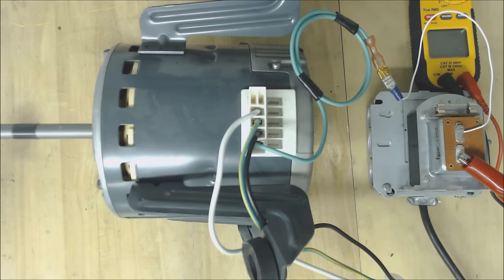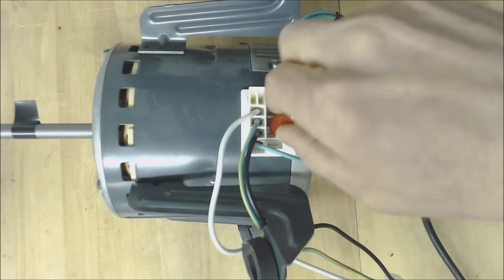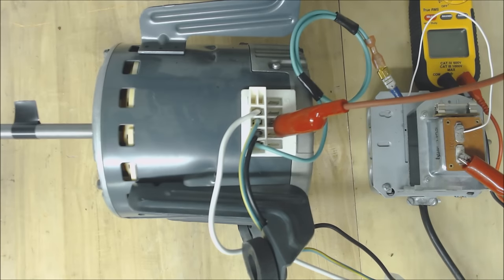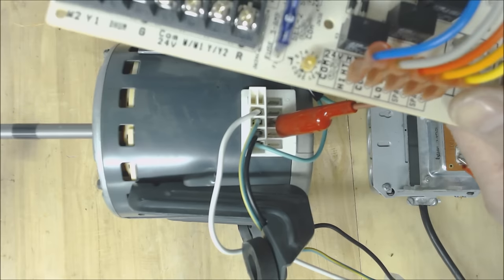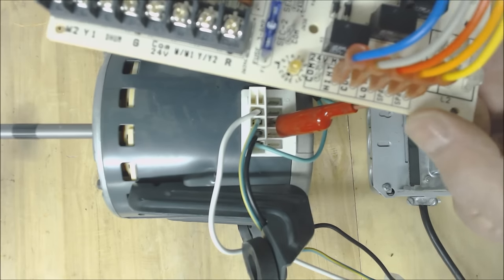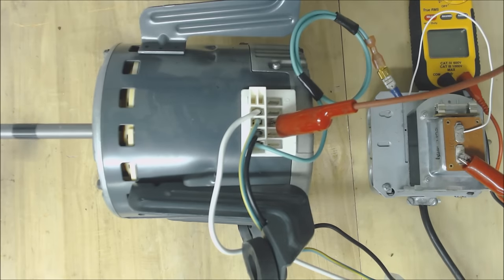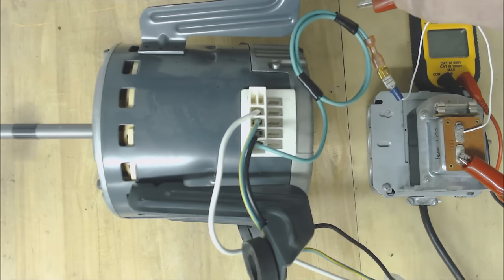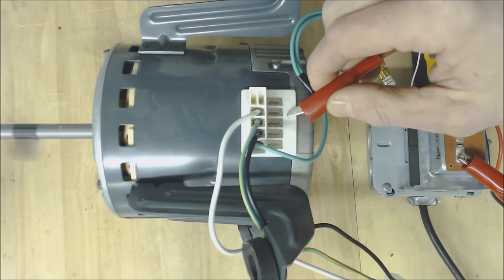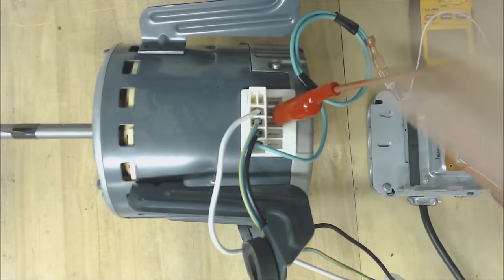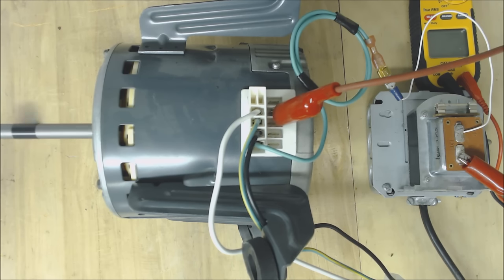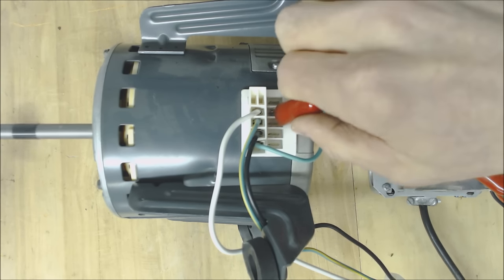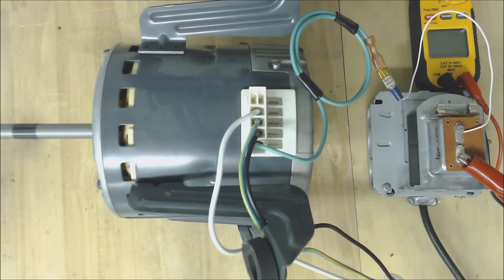It should be able to just maintain a constant airflow. We're just going to go ahead and check each of these speed taps. Now some of these are programmed as shown on our control board right here and some are not. Some are spares but usually what's going to happen is the motor is still going to turn on those, it's just they may not be set at an accurate speed.